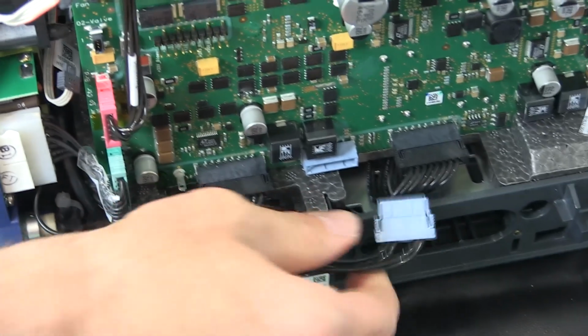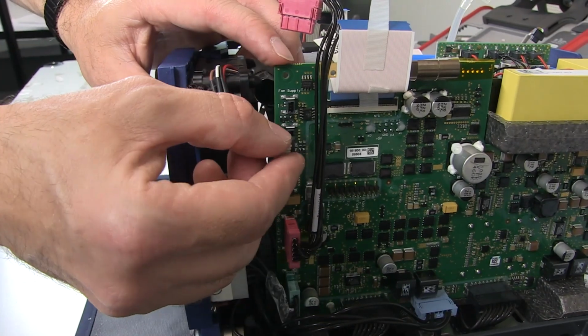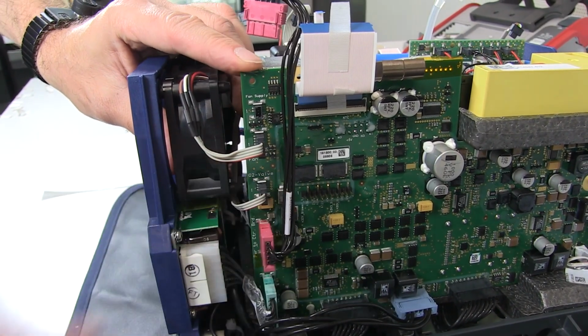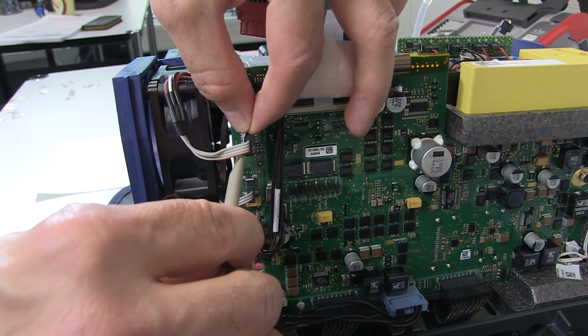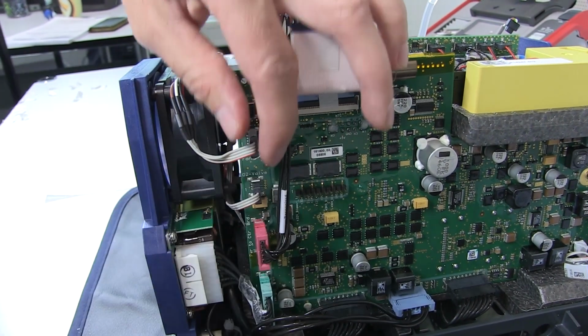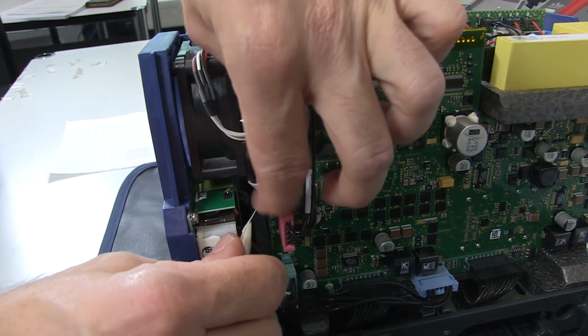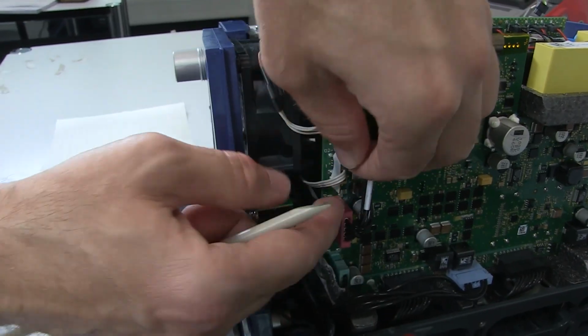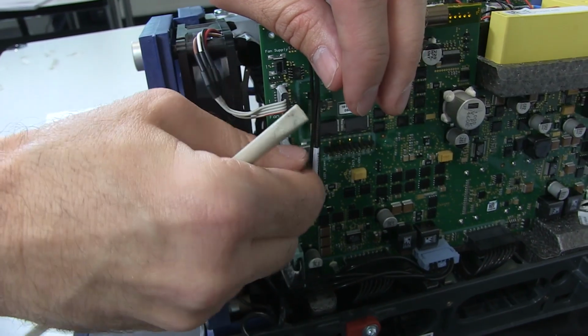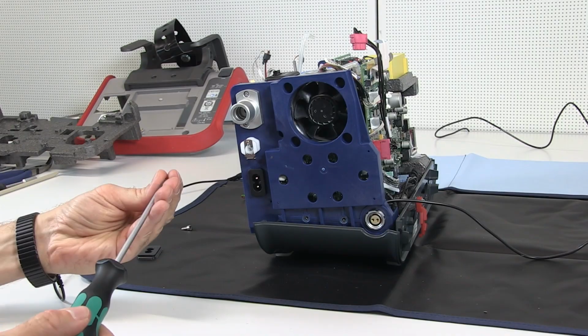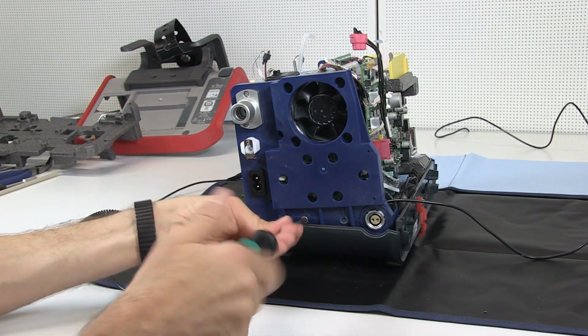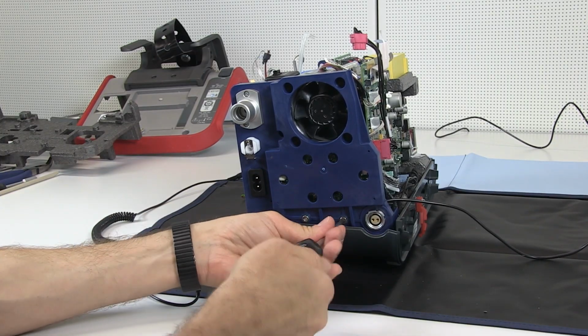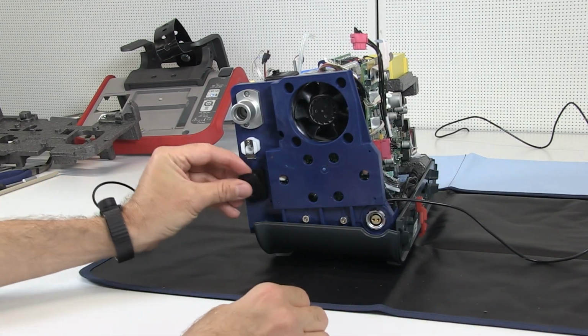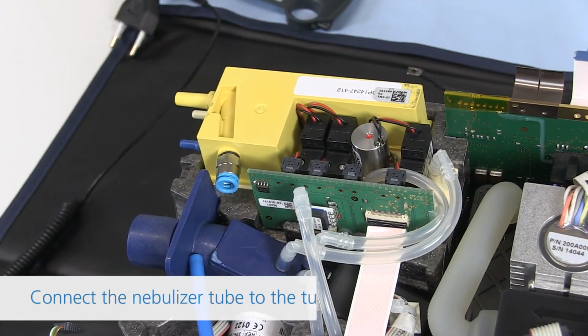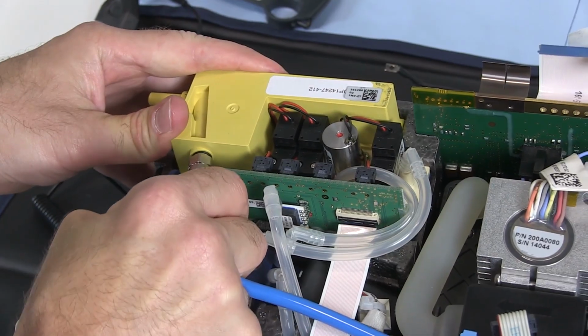Connect the green and blue plugs to the connectors on the driver board, then connect the fan and the O2 cables to their connector. Attach a strip of the carbon fibre tape around the cable plugs and connectors. Install the 2 screws on the connector plate and attach the AC plug seal to the power cord receptacle. Push the nebulizer tube into the quick release coupling. Make sure the tube is correctly installed.